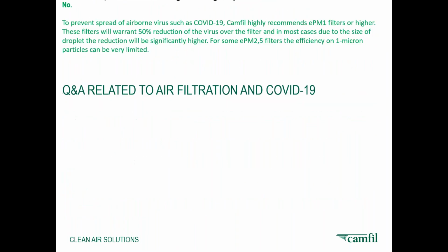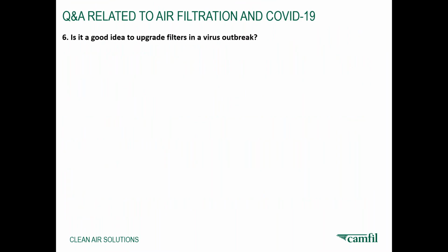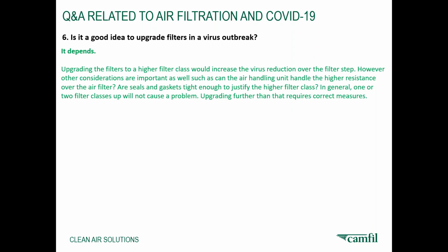Is it a good idea to upgrade filters during a virus outbreak? Some people may think it's a panic condition and that filters need to be changed. The answer is it depends - we recommend upgrading as per your maintenance cycle. There's no need to panic and think we need to upgrade the system, though we should consider whether the air handling unit can handle higher resistance over the filters. In this situation, we need to make sure the seals and gaskets are tightly screwed so there is no leakage in the system.